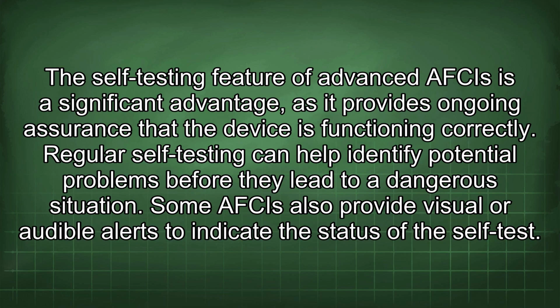The self-testing feature of advanced AFCIs is a significant advantage, as it provides ongoing assurance that the device is functioning correctly. Regular self-testing can help identify potential problems before they lead to a dangerous situation. Some AFCIs also provide visual or audible alerts to indicate the status of the self-test.